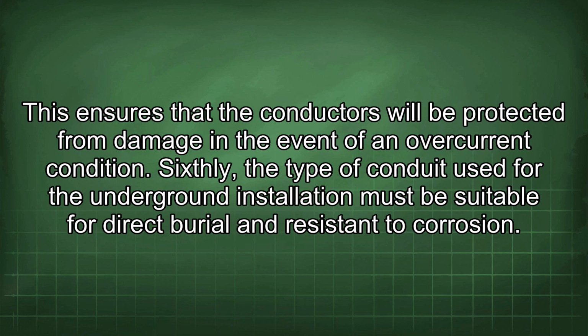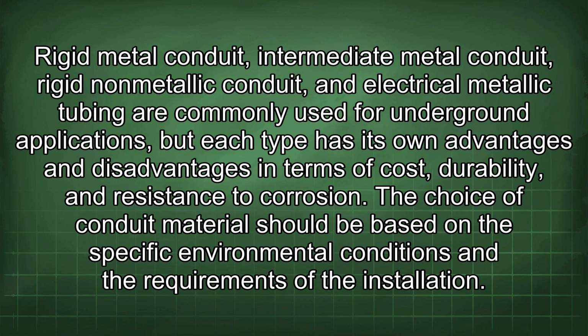Sixthly, the type of conduit used for the underground installation must be suitable for direct burial and resistant to corrosion. Rigid metal conduit, intermediate metal conduit, rigid non-metallic conduit, and electrical metallic tubing are commonly used for underground applications, but each type has its own advantages and disadvantages in terms of cost, durability, and resistance to corrosion. The choice of conduit material should be based on the specific environmental conditions and the requirements of the installation.